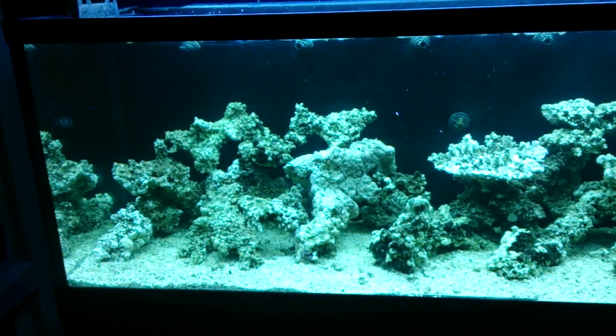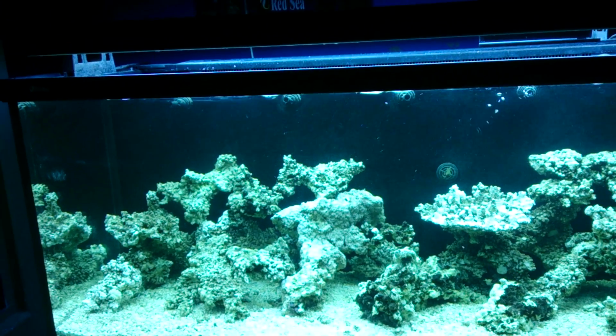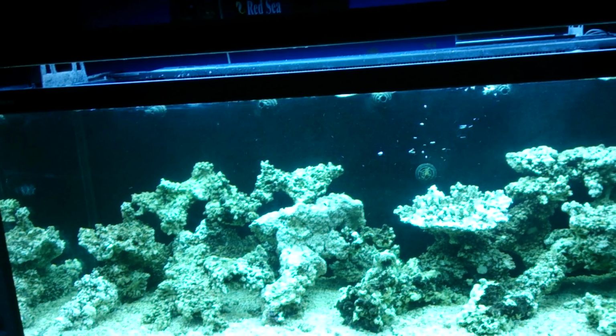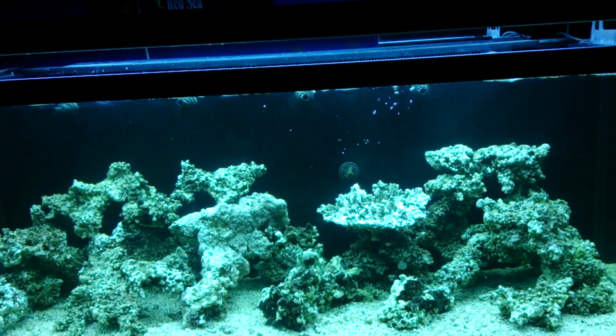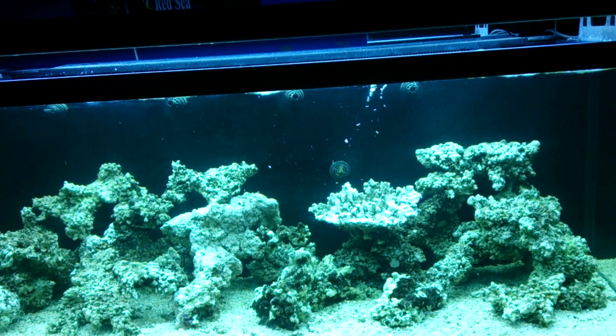The reason why you have bigger issues is it's harder to chill water than it is to heat it. So in a perfect world, you get a chiller, such as that. The chiller goes down in the cupboard, but preferably not. This Red Sea cabinet's designed so it's short at the bottom, so air can actually flow through it. But if it's a really hot day, it's advisable to open up the cabinet so air gets through, because good airflow makes the chiller more efficient.